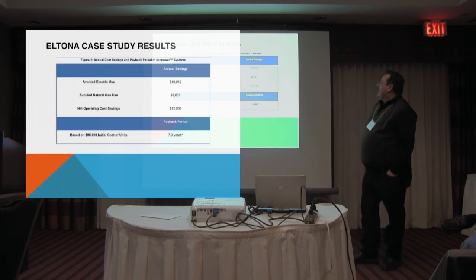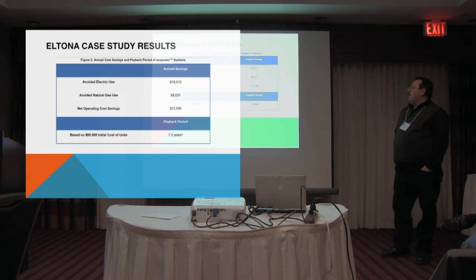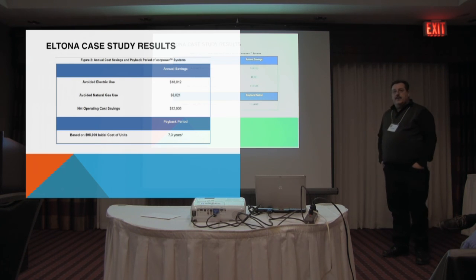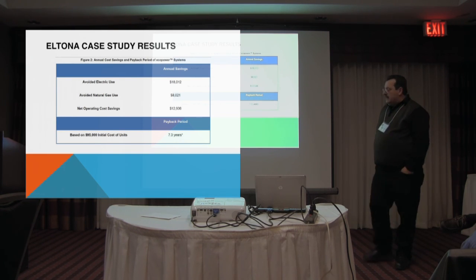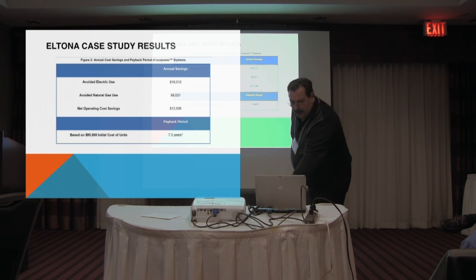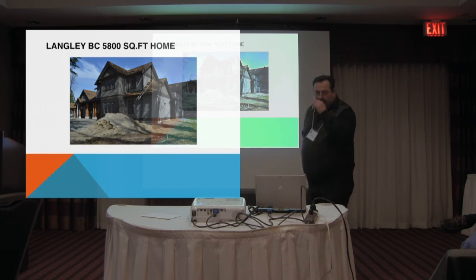So the avoided electrical use is $18,000 in this case. The avoided natural gas use was $8,000. Net operating cost savings $12,936. Payback period in that particular situation, based on $95,000 initial cost for the 2 units, is 7.3 years. So there's a lot of variables when you look at this technology, and you have to look at everything.